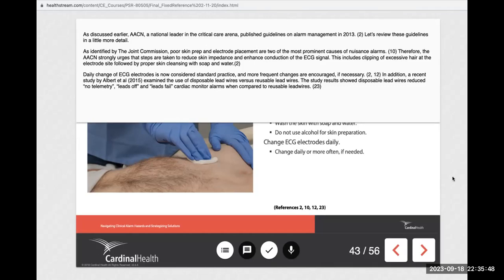As identified by the Joint Commission, poor skin prep and electrode placement are two of the most prominent causes of nuisance alarms. Therefore, the AACN strongly urges that steps are taken to reduce skin impedance and enhance conduction of the ECG signal. This includes clipping of excessive hair at the electrode site, followed by proper skin cleansing with soap and water. Daily change of ECG electrodes is now considered standard practice, and more frequent changes are encouraged if necessary. In addition, a recent study by Albert et al., 2015, examined the use of disposable lead wires versus reusable lead wires. The study results showed disposable lead wires reduced no telemetry, leads off, and leads fail cardiac monitor alarms when compared to reusable lead wires.